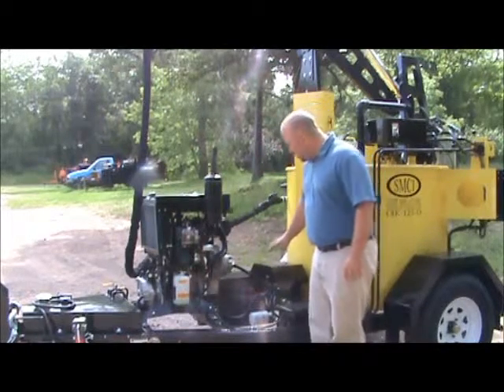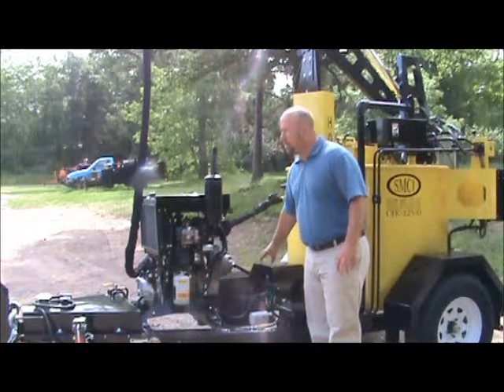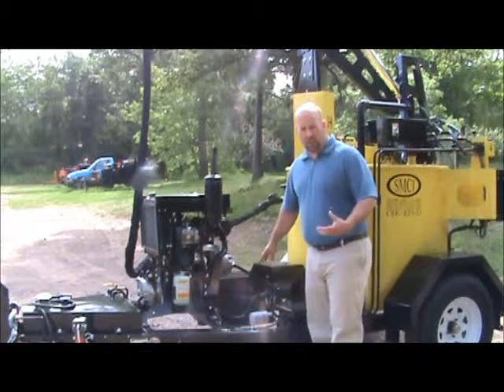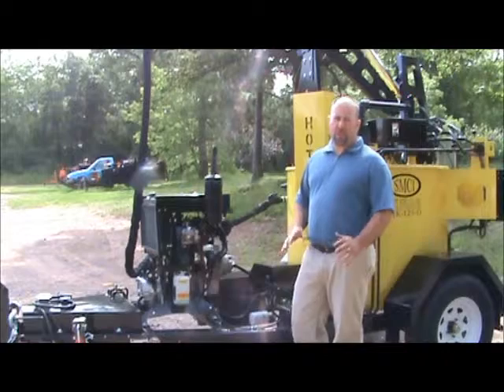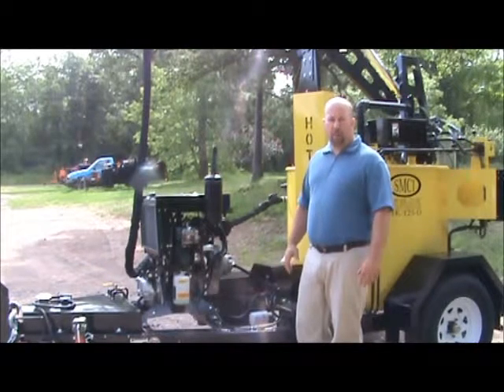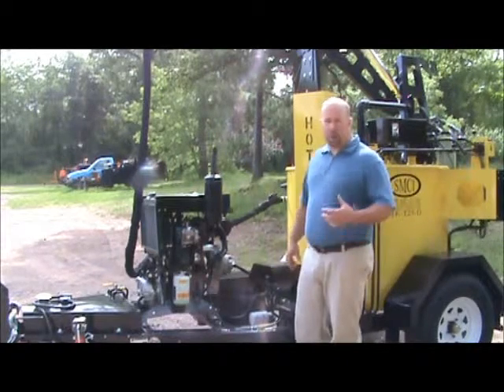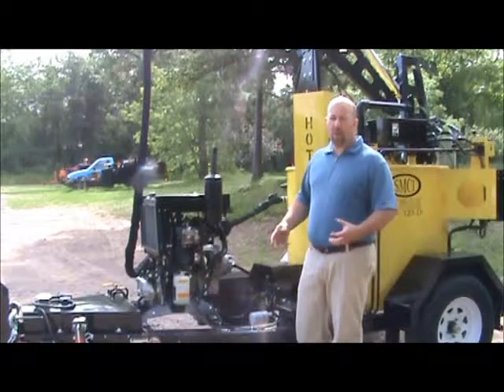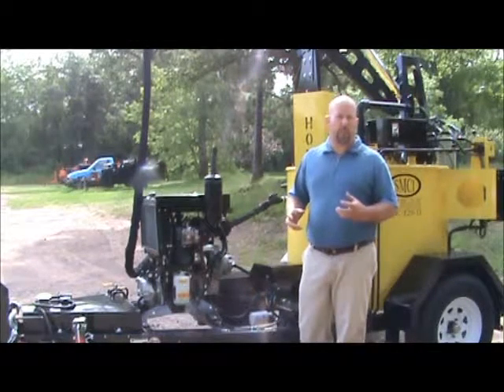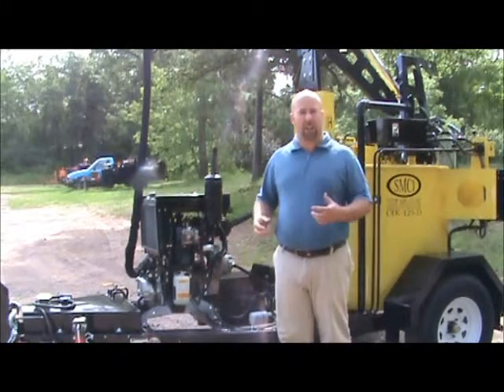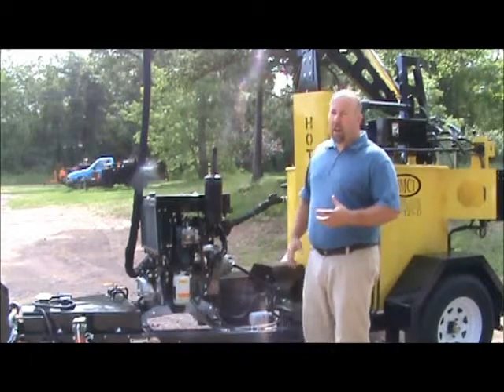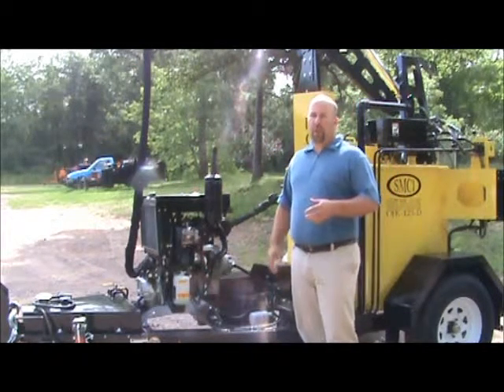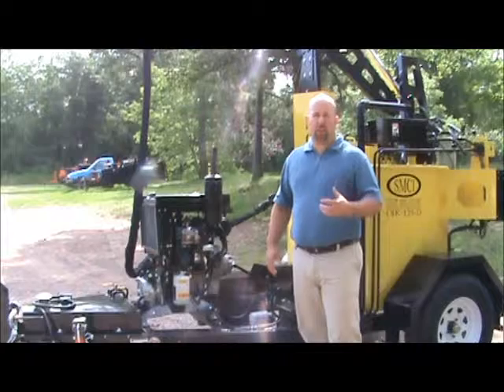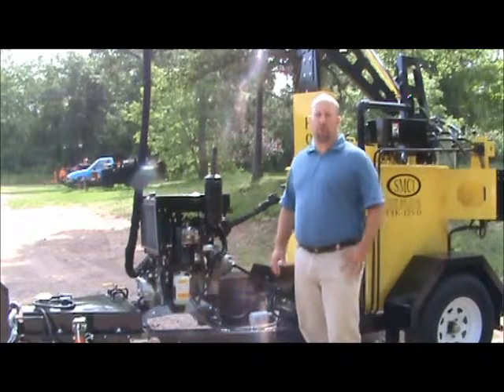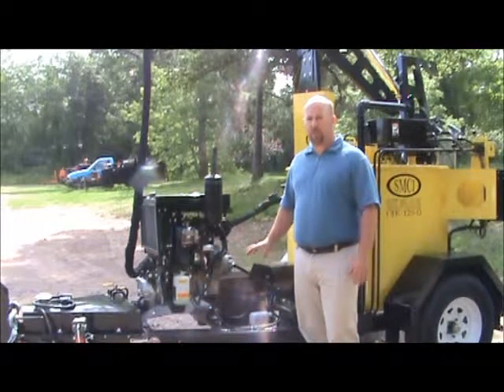We're going to zoom in on some of the features and items on here so you can see some of the adjustments. The burner is set from the factory to run very efficiently. If you notice when you're operating that it starts to smoke, we either need a burner adjustment or we need to replace some of the consumable parts like nozzles and nose cones on the burner. This burner should burn for 500 to 1,000 hours before we need to do anything with nozzles and stuff like that.